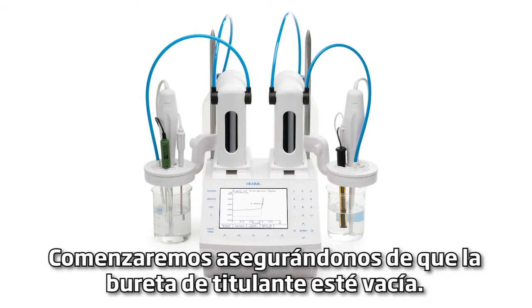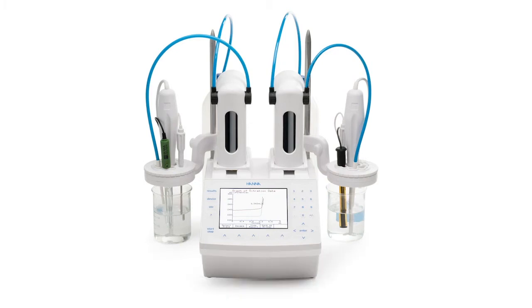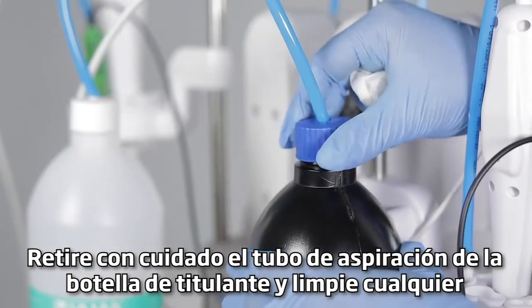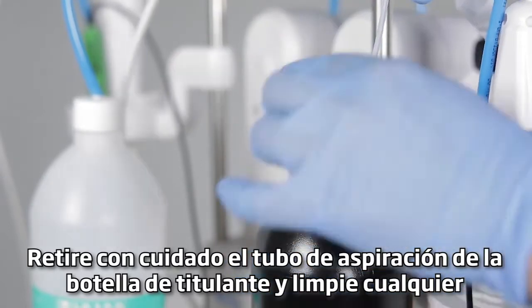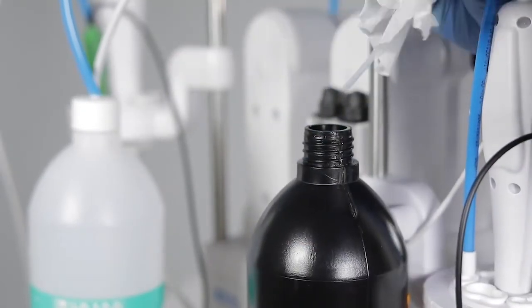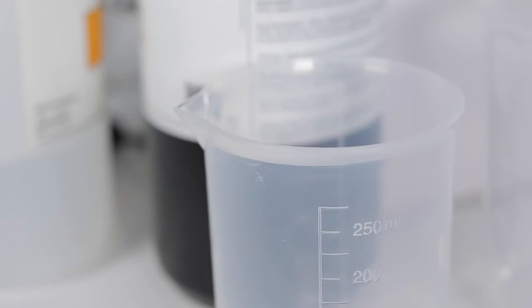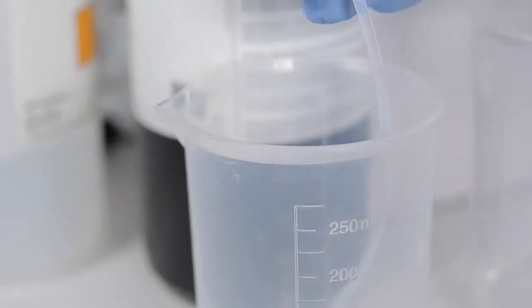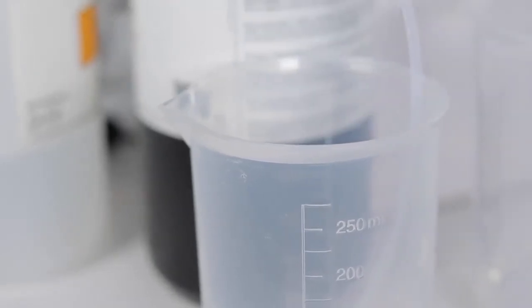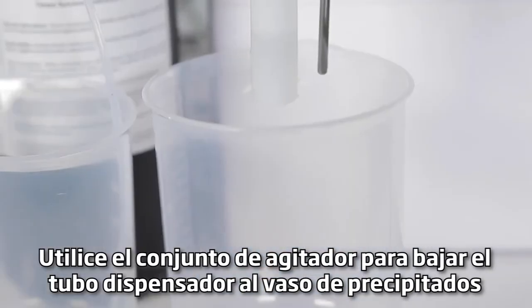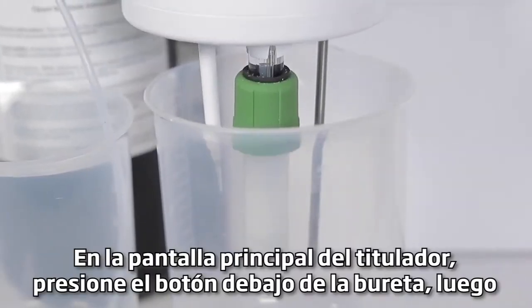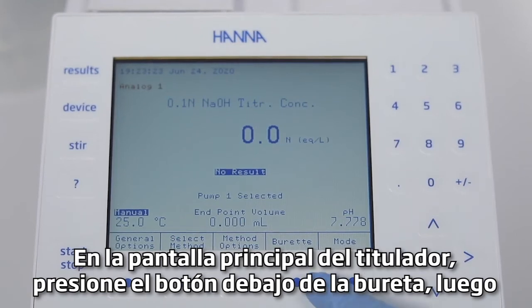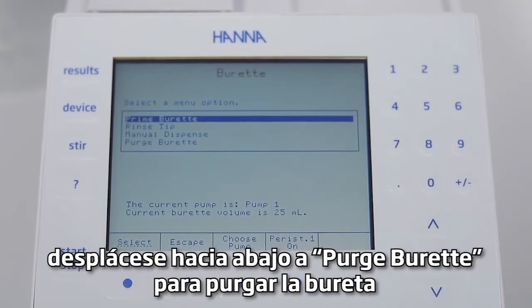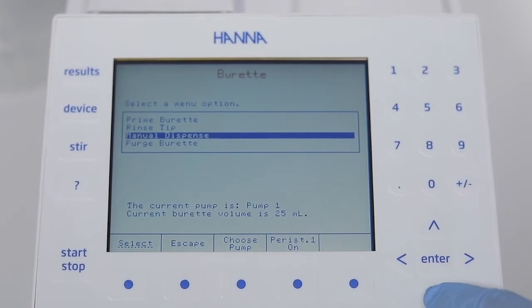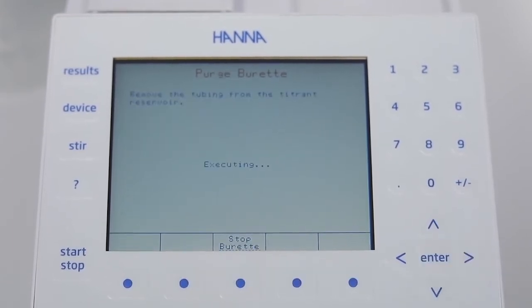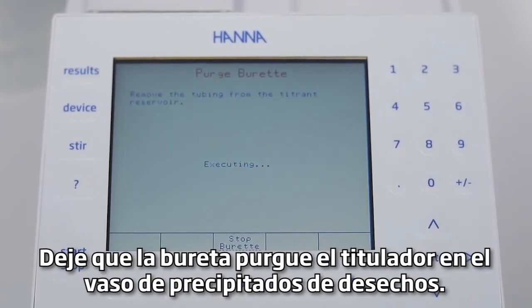We will start by making sure that the buret is emptied of titrant. Carefully remove the aspiration tube from the titrant bottle and wipe off any titrant with a lab tissue. Use the stirrer assembly to lower the dispensing tube into the waste beaker. On the main screen of the titrator, press the button underneath Buret, then scroll down to Purge Buret. Then press Enter. Allow the buret to purge the titrant into the waste beaker.